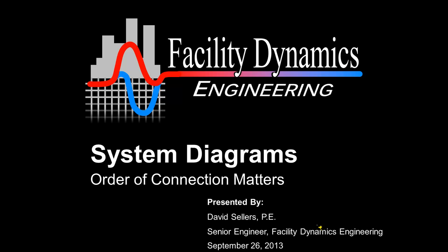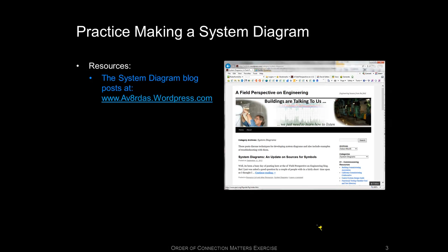Basically, what I do is I have a virtual chilled water plant that I created in SketchUp, and we use that model as the basis for the system diagram. The resources to support your doing this, I did a whole string of blog posts about system diagrams. It's a technique I was taught almost virtually the first day I started work back in 1976, and I've used it ever since then, both as a designer and as a commissioning provider. It's really a great way to understand the system, to use the system perspective, which is critical to design and operations and commissioning.